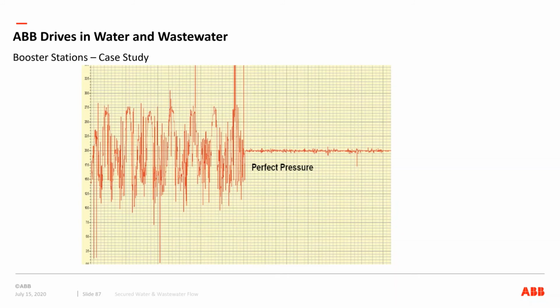Will's got a question. He says, what type of control should we use a drive for in treatment water? Torque control, speed control, and why? Well, it really comes down to what type of pump you have. If you've got a centrifugal pump, I would go for speed control. Pumping water, I don't want to call it easy, but it's pretty easy when we look at other processes. It's not like pumping concrete or pumping pickles or pumping wastewater. Pumping clean water is pretty easy. So I would look for more speed control. It's easier to set up. It's easier to do. The VFDs out of the box typically are designed to handle it. You don't need extra sensors.